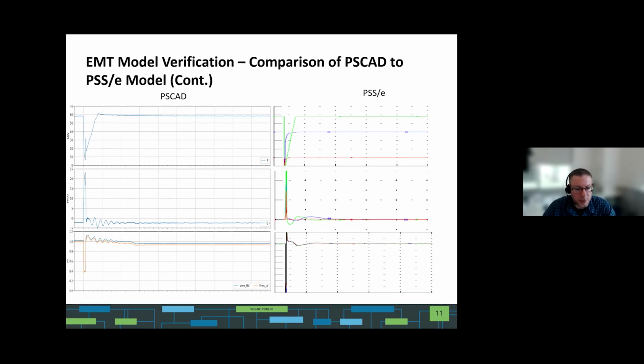What you're looking for is that PSSE, remember, is an averaged model - an approximate averaged model of the real performance of the system, whereas PSCAD is meant to be a more aligned representation of the actual system. As long as your averaged performance is aligned with the PSCAD performance, that's what we consider a good benchmark, and acceptable.